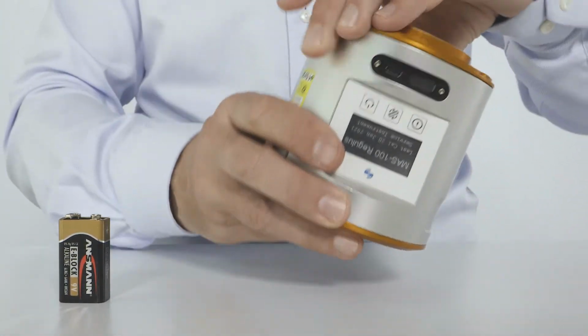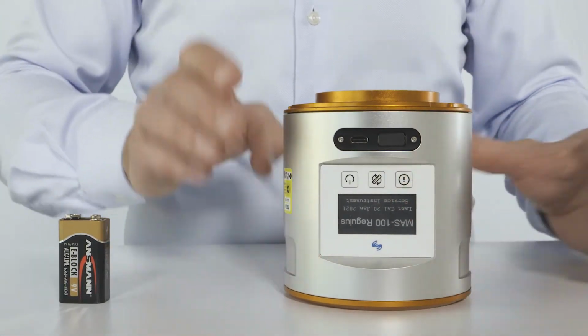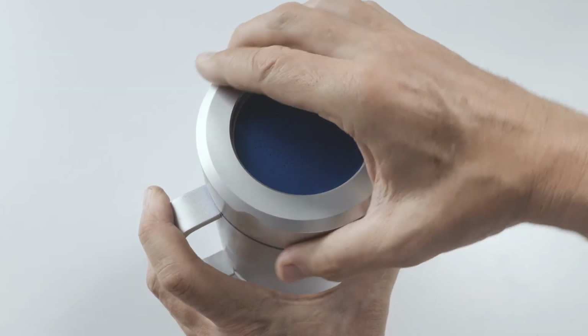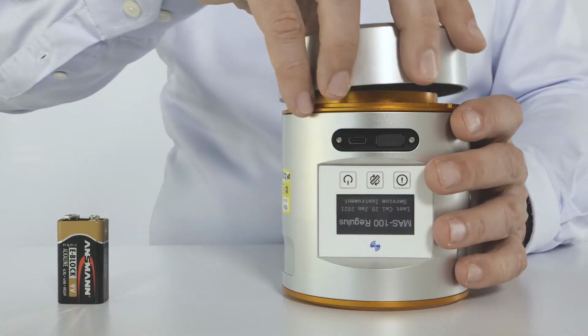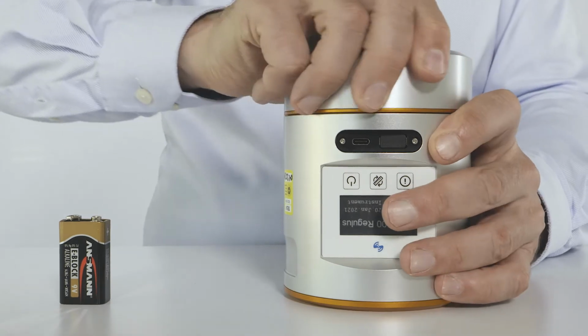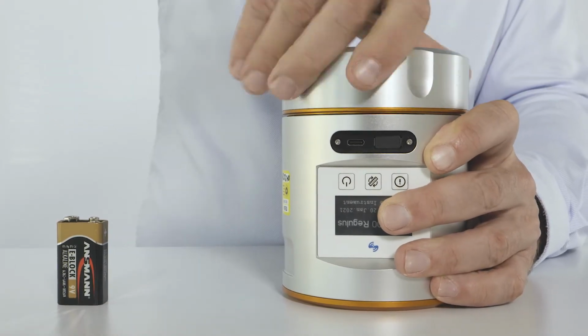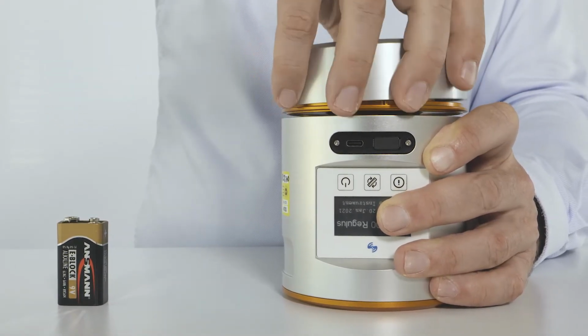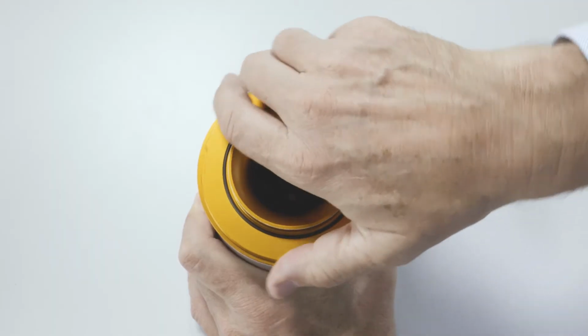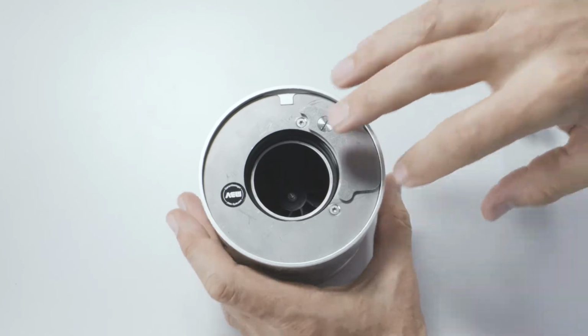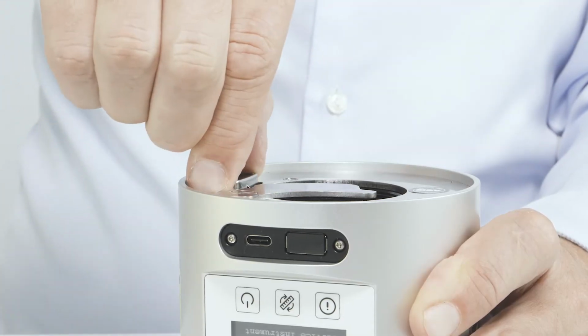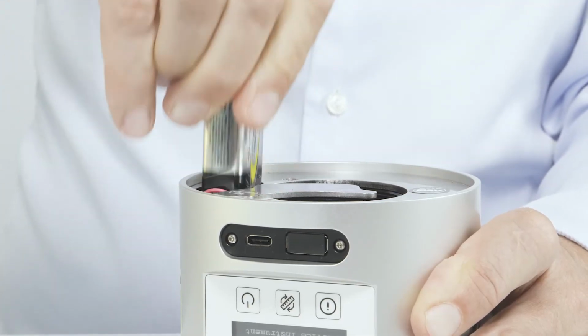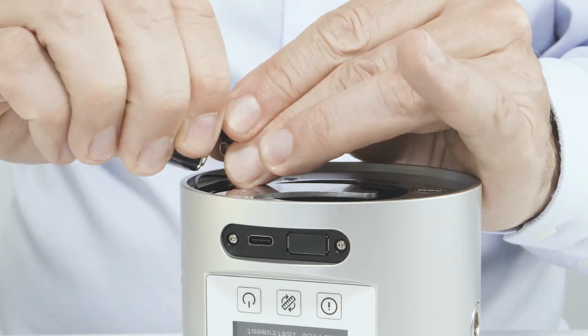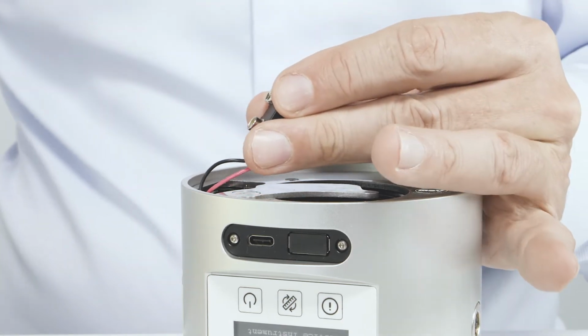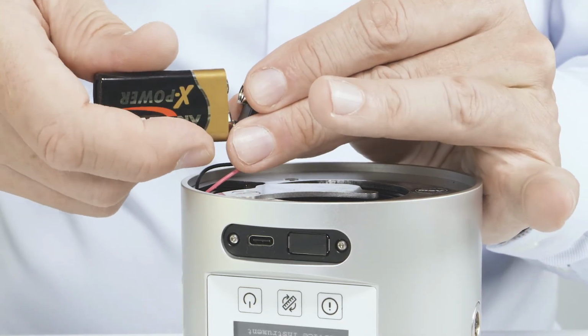The battery is located under the base plate of the MAS-100 Regulus. Use a perforated lid of any MAS-100 microbial air sampler to access the battery compartment. Turn counterclockwise until you can remove the base plate. Open the battery retainer and pull the battery out of its compartment. Unplug it from the connector and replace it with the new battery.